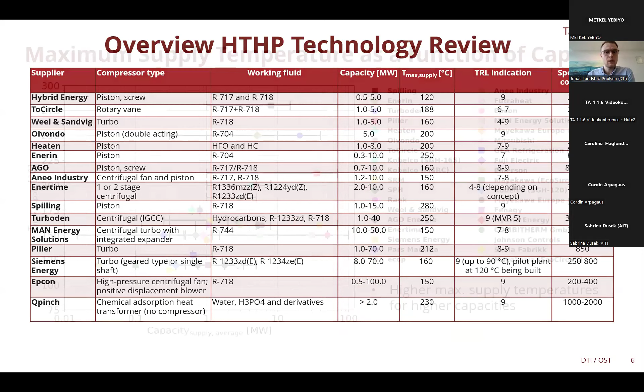Let's take a deeper look using some metadata. What I have plotted here is each of the suppliers has a corresponding dot and color in this figure, with capacity on the x-axis - please note this is logarithmic - and the maximum supply temperature the heat pump system can deliver on the other axis. I think one of the trends we could see is that if you want heat pumps at the very high maximum supply temperatures, that also corresponds to the ones having a higher capacity. So there is somewhat of a trend, maybe not linear, but at least a trend that higher maximum supply temperatures also correspond to higher capacities.